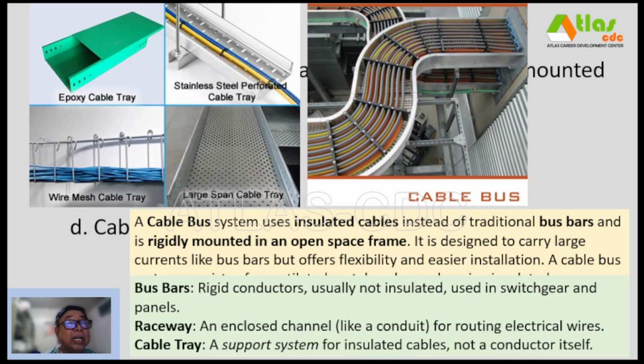Versus a bus bar. Ang bus bar is a rigid conductor, usually not insulated and used in switchgear and panels. Raceway, on the other hand, is an enclosed channel like a conduit for routing electrical wires. And cable tray is a support system for insulated cables, not a conductor itself. So itong pinaka-tray niya mismo, no?